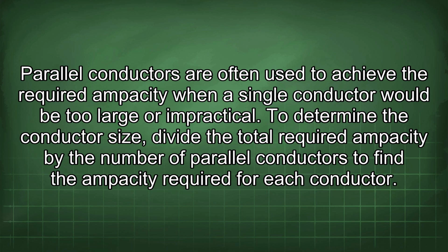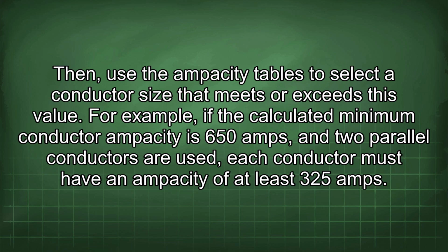Parallel conductors are often used to achieve the required ampacity when a single conductor would be too large or impractical. To determine the conductor size, divide the total required ampacity by the number of parallel conductors to find the ampacity required for each conductor. Then, use the ampacity tables to select a conductor size that meets or exceeds this value. For example, if the calculated minimum conductor ampacity is 650 amps and two parallel conductors are used, each conductor must have an ampacity of at least 325 amps.